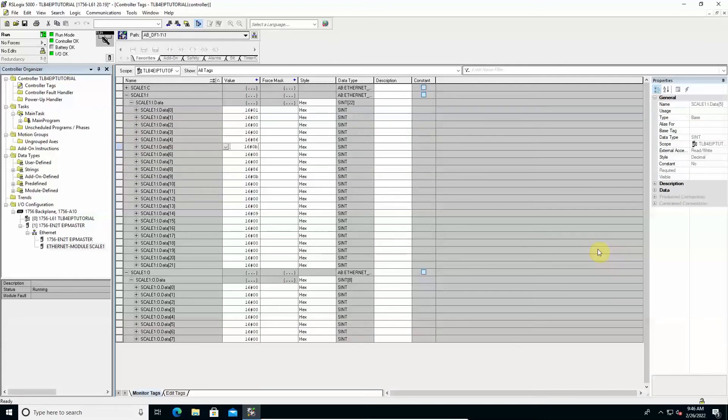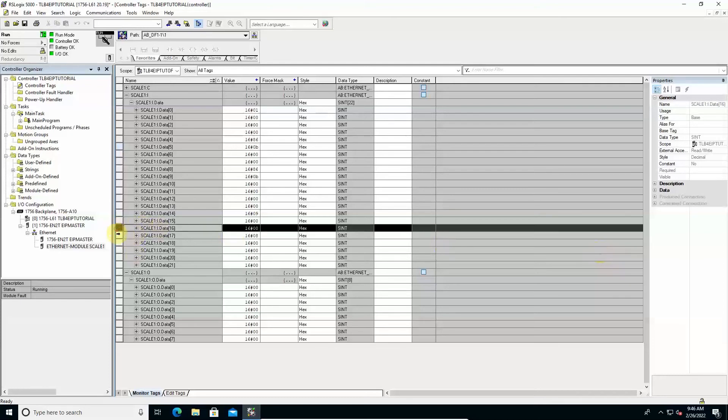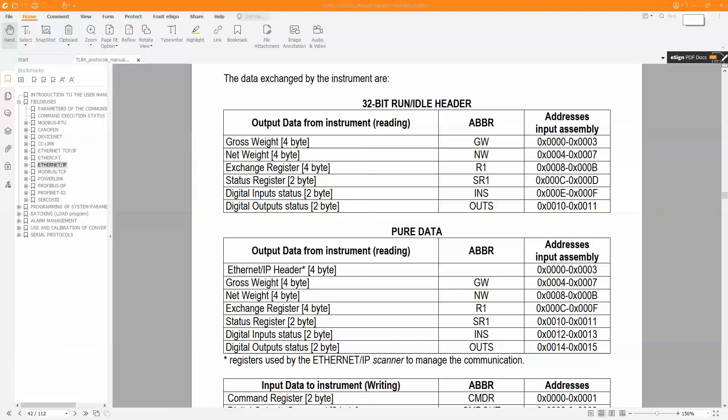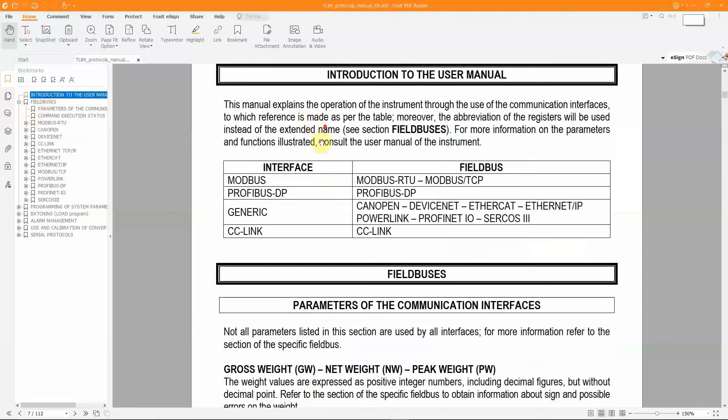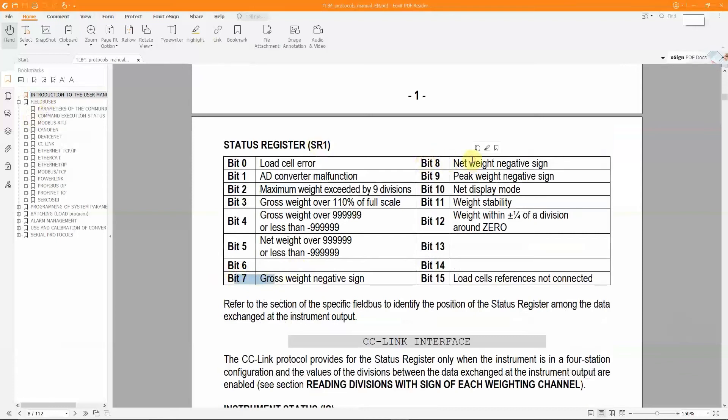The information about the sign of the weight values is available in addition to other information regarding the operating status of the instrument in the bits of the status register. In the protocols manual, a specific table shows the meaning assigned to each of the 16 bits that make up this field. And particularly bits 7 and 8 indicate the sign of gross and net weight equal to 1 when the corresponding current weight is negative. Bit 11 is equal to 1 if the current gross weight is stable otherwise it shows 0. Bit 10 is equal to 1 if the tare value is applied by the instrument to the calculated net weight.